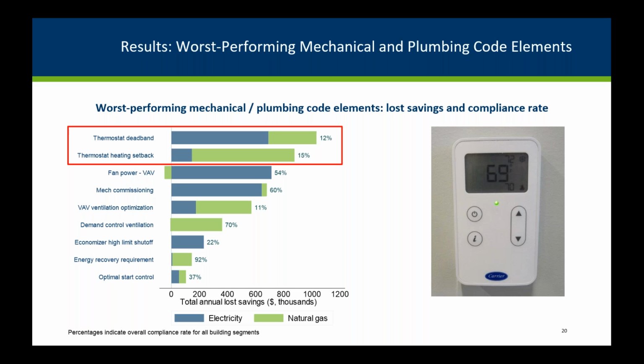The top 2 worst performing elements that we found in the field are related to HVAC thermostat control, which are deadband and heating setback. Thermostat deadband is the temperature difference between cooling and heating set points, and code requires a minimum 5-degree difference. In drawings, this was not often documented. In some cases, we found that it was documented, but with non-compliant values. In the field, we observed non-compliance in many instances. This picture here is one example, which shows a deadband of only 2 degrees.